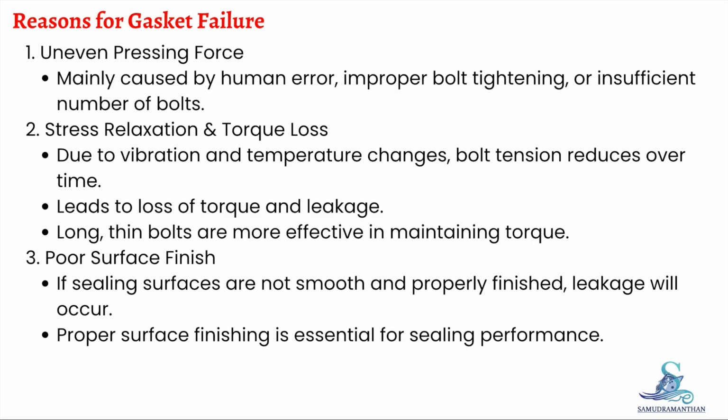Stress relaxation and torque loss. Due to vibration, temperature changes, or long usage, bolt tension decreases over time. This leads to loss of torque and eventual leakage. Using long and thin bolts helps in maintaining torque for longer periods.